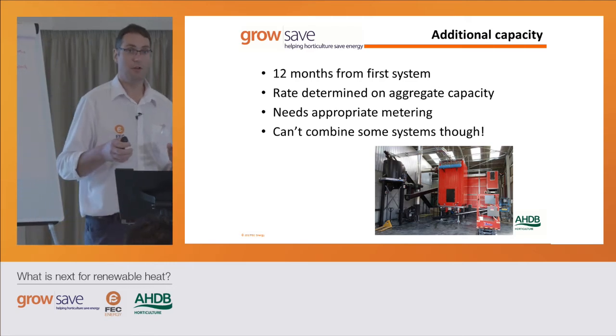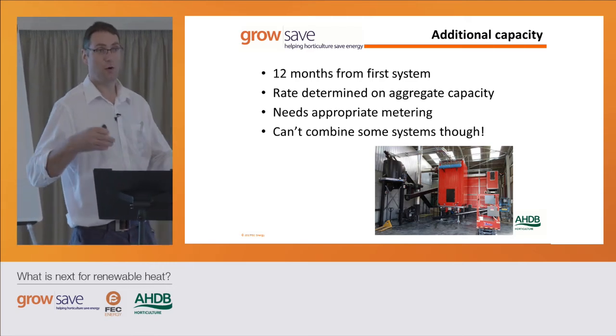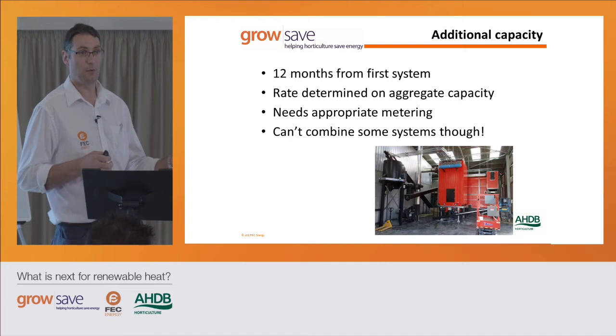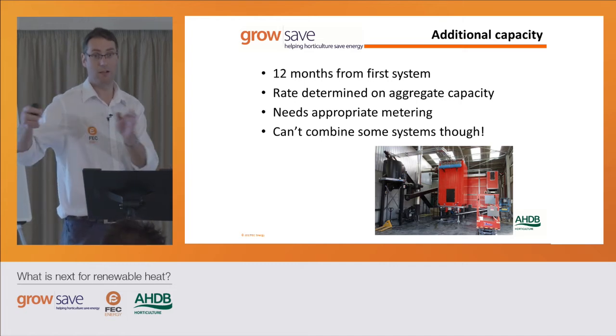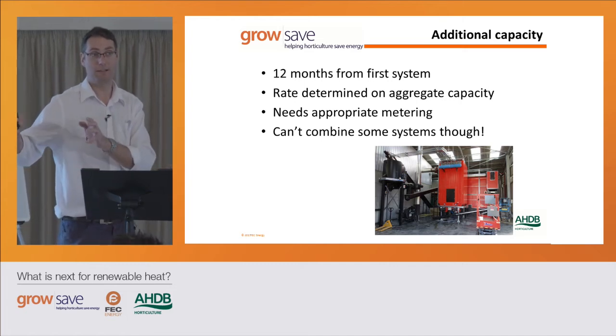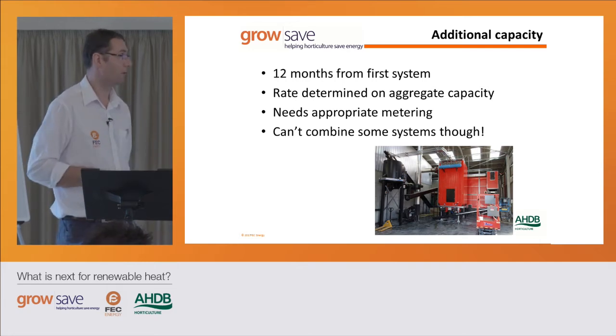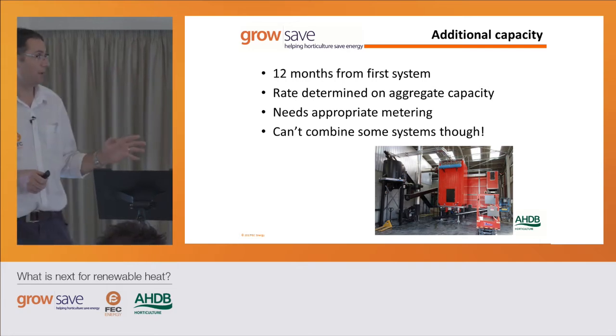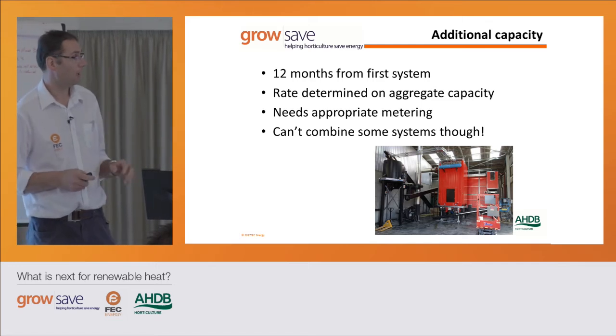So as the rates go up, if you've not quite got enough capacity in your existing 1 megawatt system, you can just add another boiler of the appropriate size to get you over that extra requirement, and still get a reasonable return without jeopardizing your first one, if you're post 12 months.